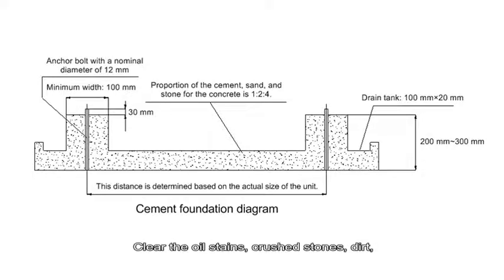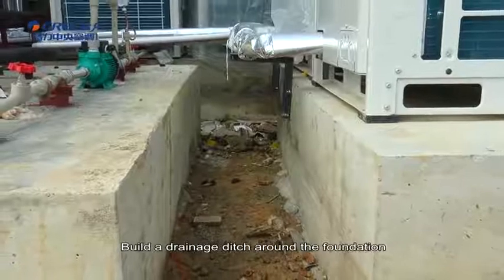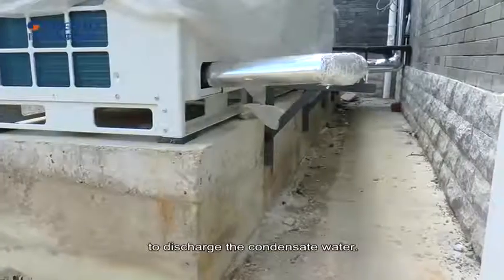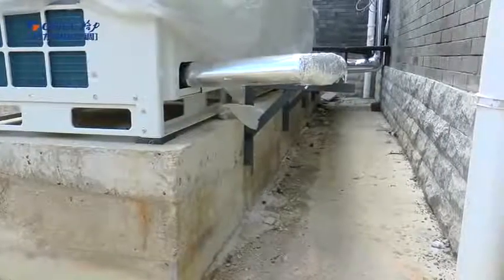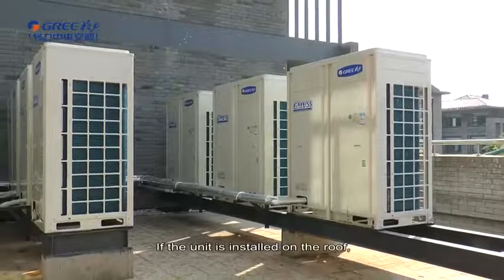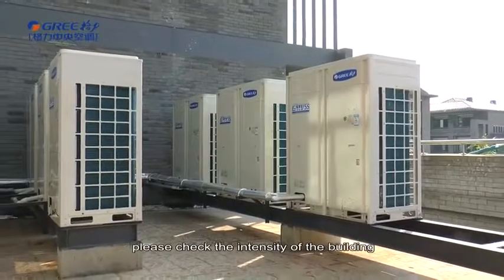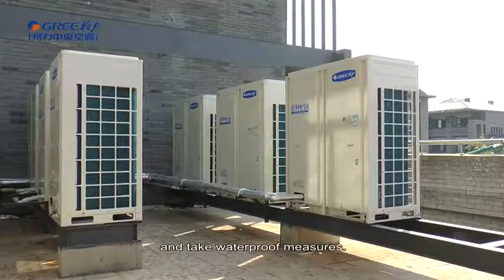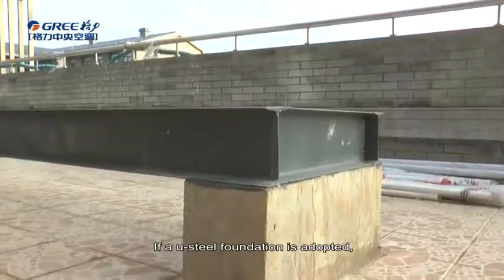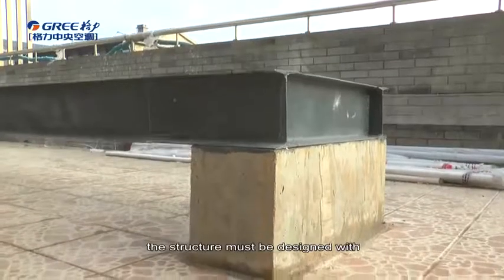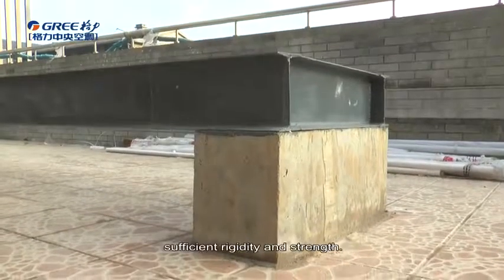Clear the oil stains, crushed stones, dirt and water in the reserve borehole of the foundation, and install a temporary cover before installing bolts. Build a drainage ditch around the foundation to discharge the condensed water. If the unit is installed on the roof, please check the intensity of the building and take waterproof measures. If a U-steel foundation is adopted, the structure must be designed with sufficient rigidity and strength.